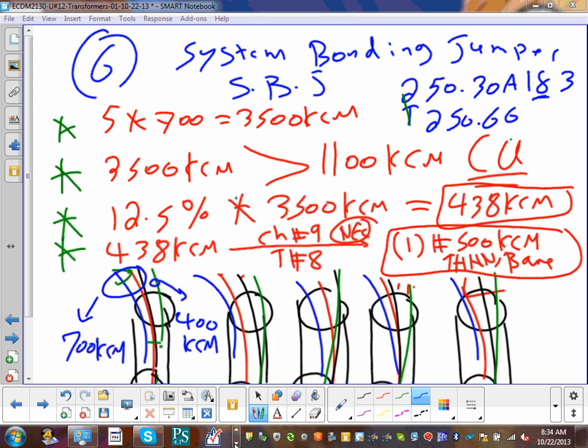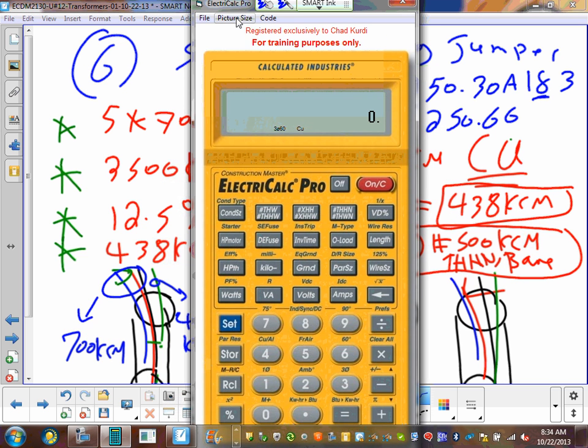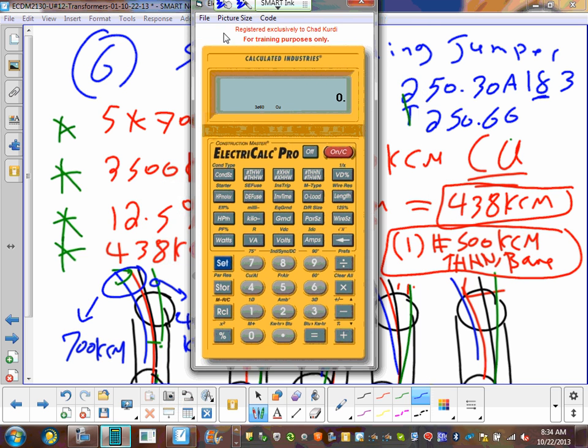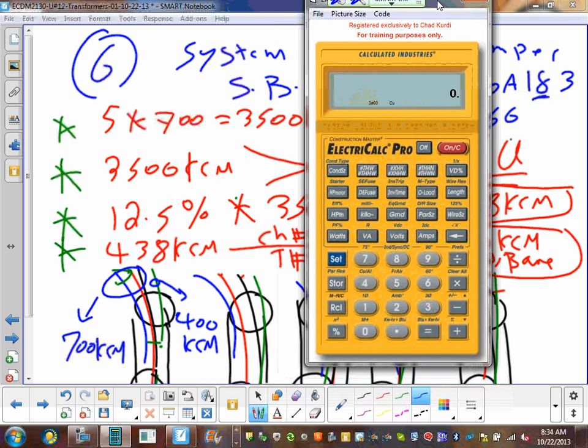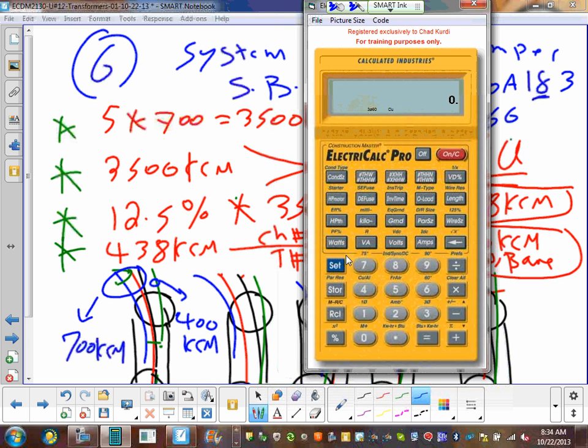Where's my calc? There you go. We've done all this that we just did on this calculator. Absolutely. Well, you have to know what you're doing, medium voltage. Okay, let's just size the conduit and I'll show you. Let's go size the conduit, guys. Hit Set 7, so you can set your calculator at 3-phase 75 copper. Okay? So make sure your calculator is set at 3-phase 75 copper. Yes? The ones who have it?